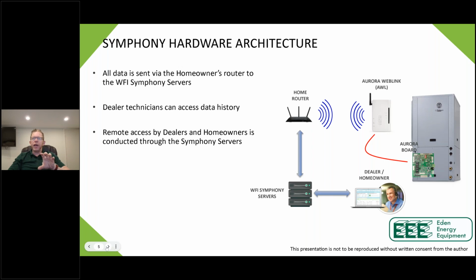The Symphony system allows us to drill into that unit and help your team. It also helps your service manager log in and assist the technician in the field. And it gives you the ability, if you have a problem with a unit, to log in before you even go out. If it's just a filter issue, you'll see that in the logs, and you won't need to send your licensed tech to pull a filter and replace it, you can send the apprentice instead. The ability to get remote access to data through the system is very impressive.